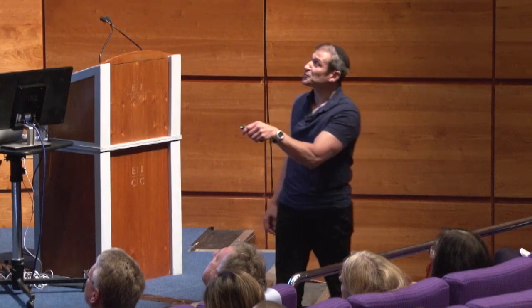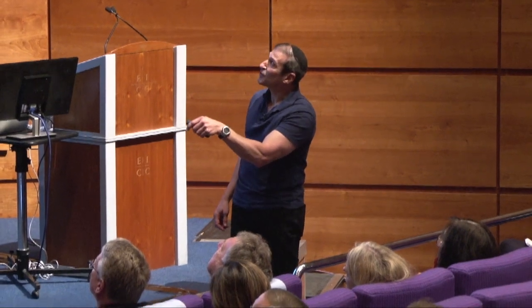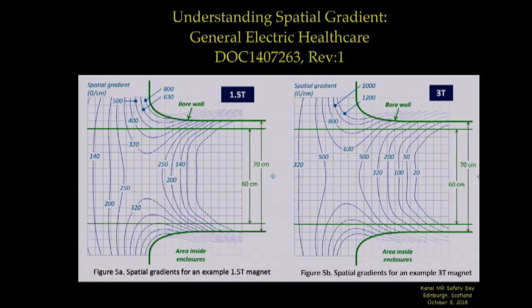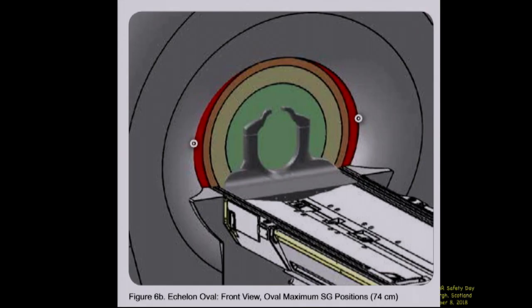This is the bore, and the patient would come in this way. If this is the bore, 1.5 and 3, this is showing you where the dBdx is in Gauss per centimeter, and here it's 140, 250, 300, here it's 800. And this one for a 3 Tesla, it goes to, here's 1,000, 1,200, do you understand? But again, where is it greatest? About here, where you put your hands on. Different manufacturer. The red shows where it's greatest.